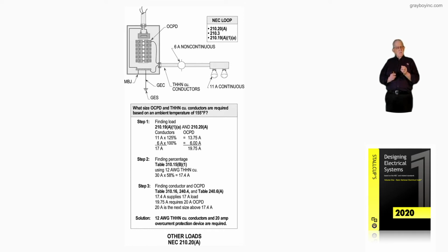And notice 70B warns you of this in 15.1.3, which lists about 3 other sections to review from Annex L to 70B that tells you, watch out for this. See if you have heating problems. So you either have to reroute it or you've got to allow for this temperature. So step 1, we do the calculations in accordance with 210.19(A)(1) and 210.20(A), conductor sizing and overcurrent. So to the left of step 1, we're sizing conductors.